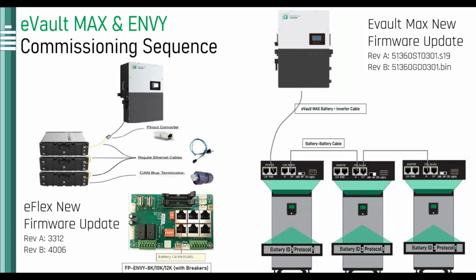Okay, so once that's set on the LCD screen, then we move forward into terminating the communication, right? We put a communication cable that's included with the battery. Communication cable from the COM parallel ports is going to go from out to in, and then you terminate the communication with the 120 ohm dip switch that's integrated into the eVault Max cabinet. Okay, and from there you take the existing wire cable that comes with the eVault Max. It's usually an RS485 cable that we used to use for communication with Solarc. You can go ahead and use the same cable, put it on the RS485 port of the eVault Max, and go ahead and put it on the battery communication port of the MB.